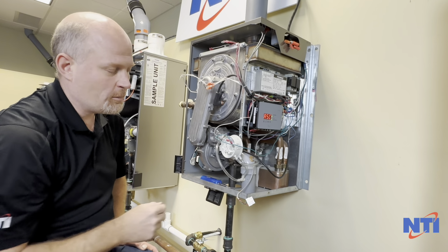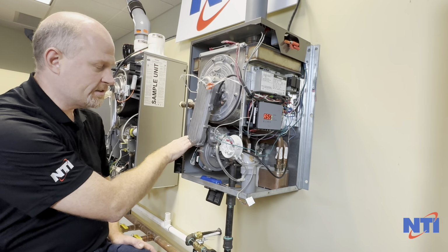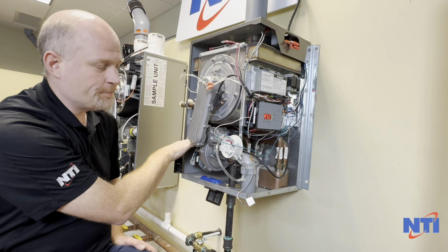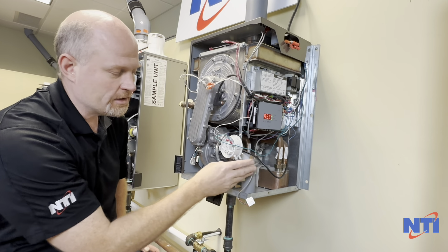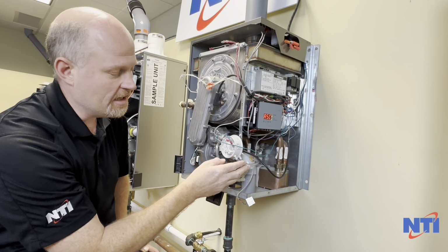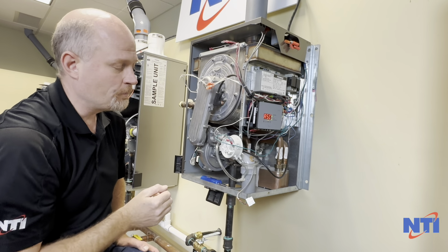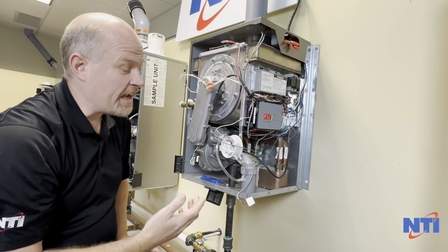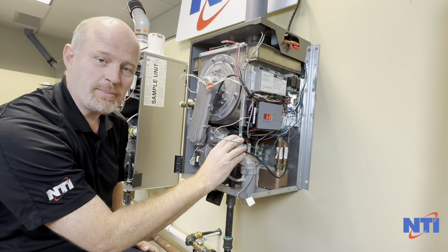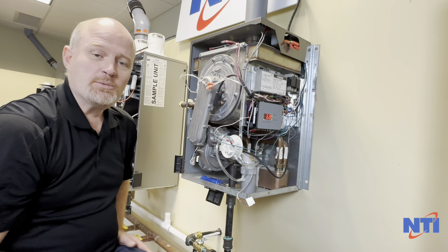So the 2 most common causes for an ASC, one is the fan is actually going bad, and number 2 is water in the tubing here. The least common is probably some sort of damage to the Sentry control, and less common than that, again, is the air switch itself is bad. So hopefully that helps you with your troubleshooting.